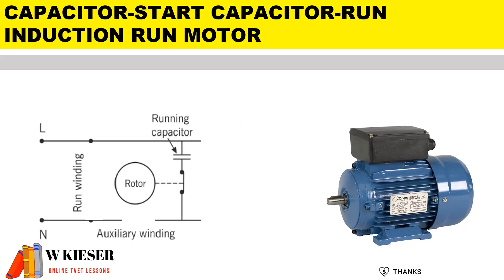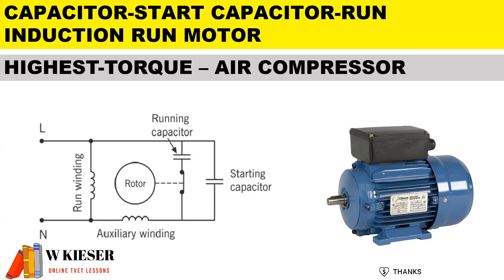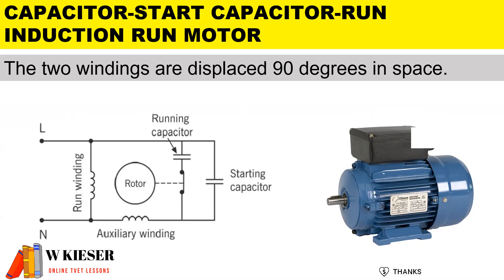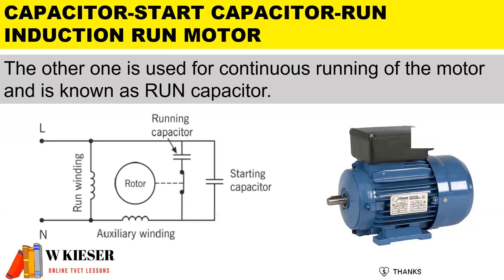This motor is known as the capacitor start capacitor run induction motor. Looking at the circuit diagram, you'll notice the run winding, the auxiliary winding, a run capacitor, and a start capacitor. It is mainly used as an air compressor and has the highest torque. The motor has a cage rotor and its stator has two windings — the main and auxiliary winding — displaced 90 degrees in space. One capacitor is used at starting, known as the starting capacitor, and the other is used for continuous running, known as the run capacitor.